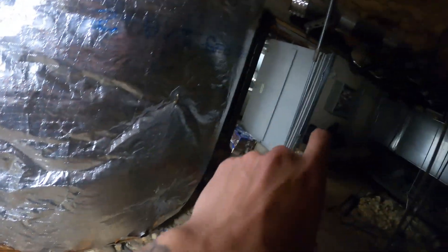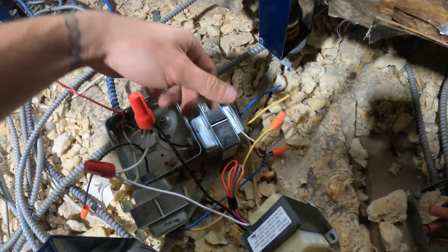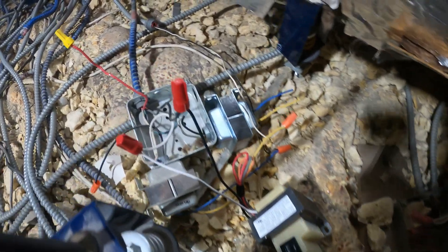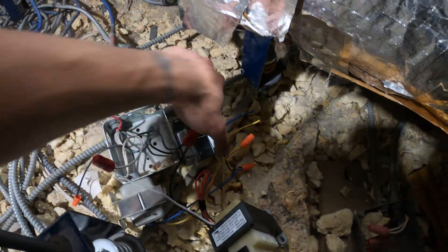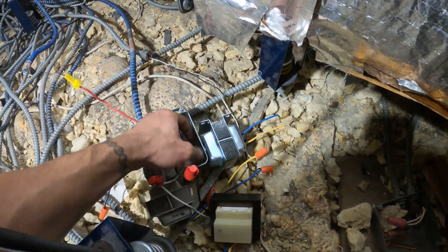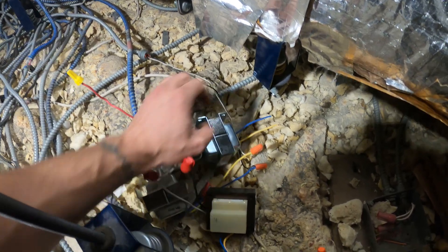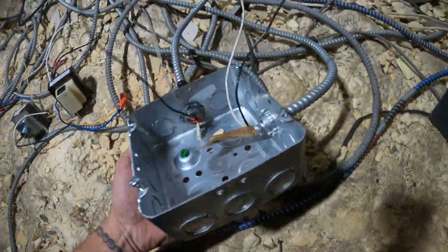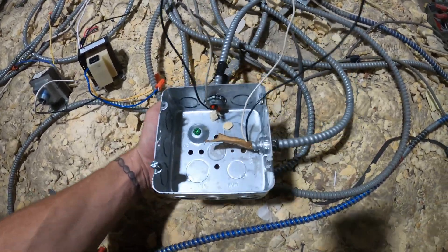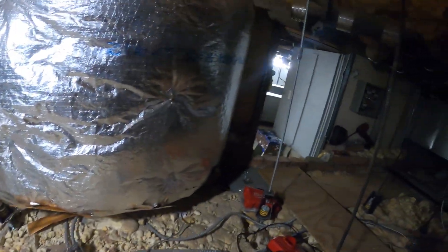This is going to be our last transformer that goes in there. Right now I want to clean up this mess — this transformer is not in use, I'm gonna take that out and separate the others. This box is going to be used just for our line voltage, and then I'm gonna tap in a BX and run that into our main box. With our two heater wires in this box, we'll make all our low voltage connections in here and all our high voltage connections in there, then run BX to our panel.